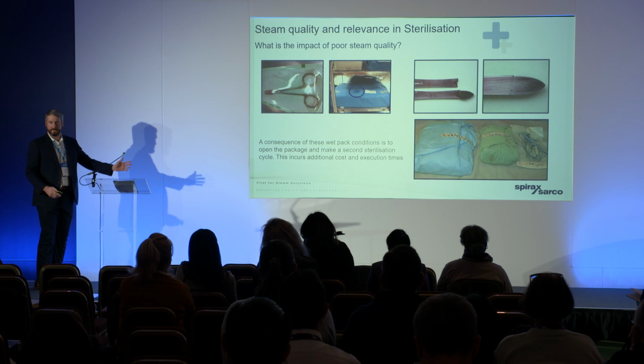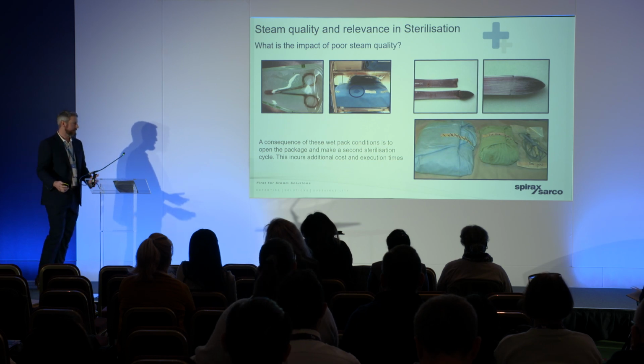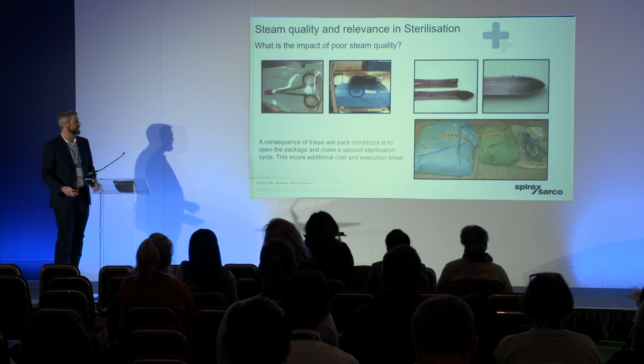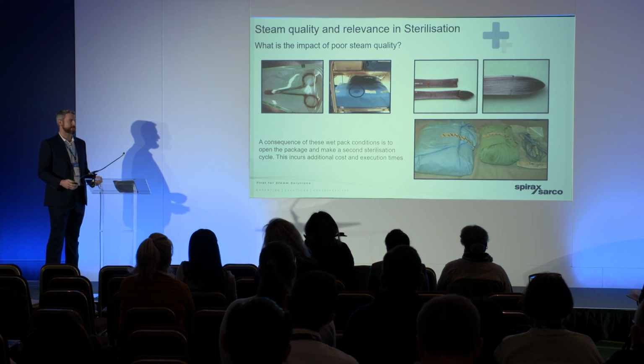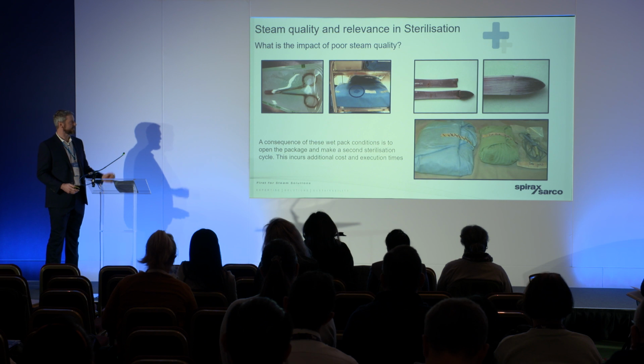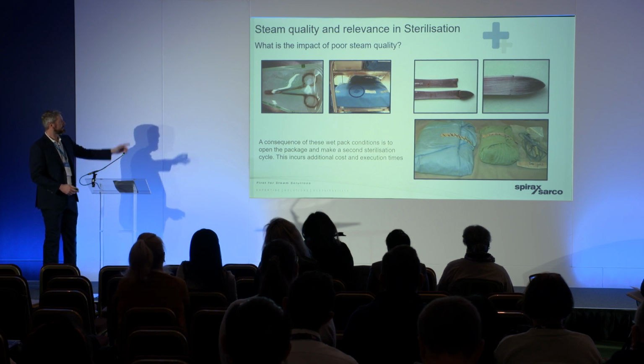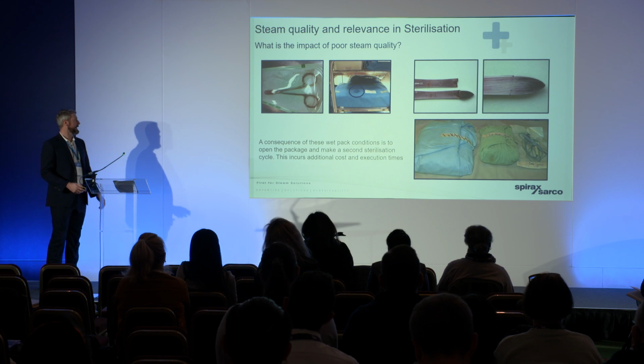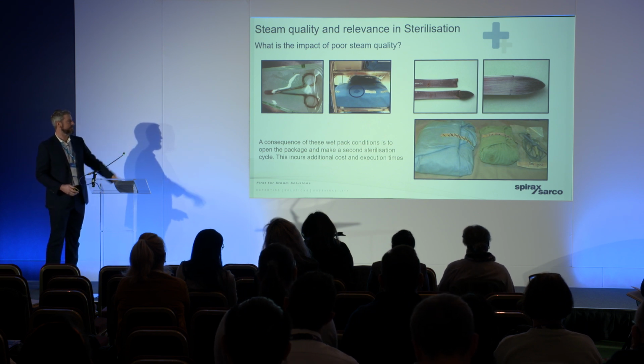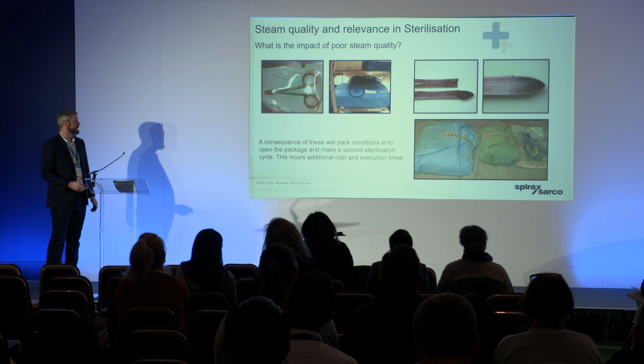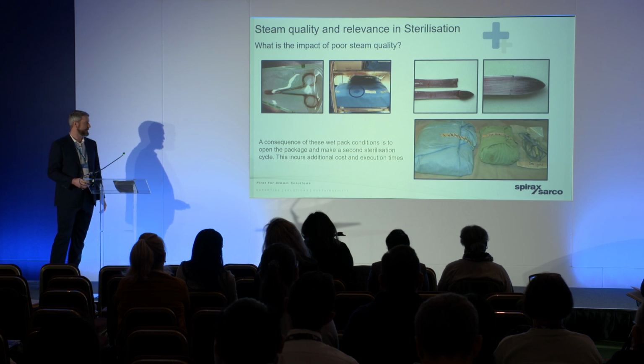The purpose of this slide is that the reduced heat transfer, the poor steam quality, and some of the quality issues that we understand you see around sterilization are visible in these images here. So some moisture left on packs. These are failed sterilizer loads, and of course, this incurs additional time and cost.